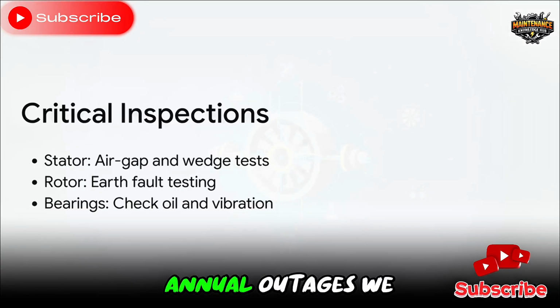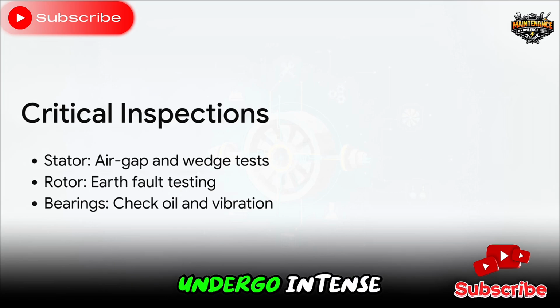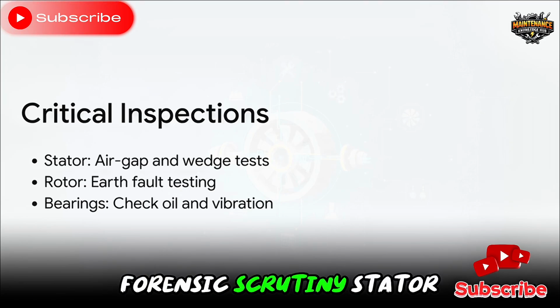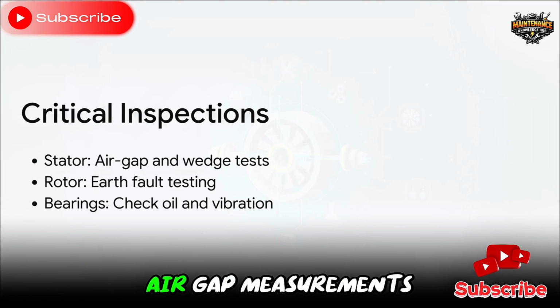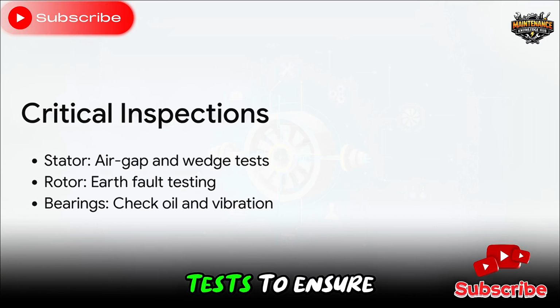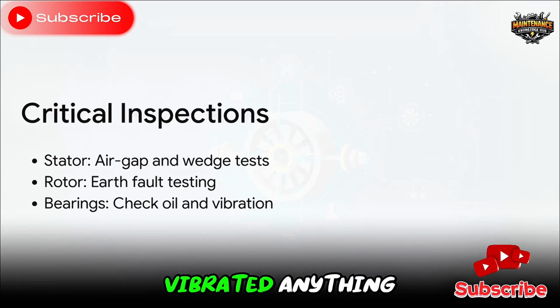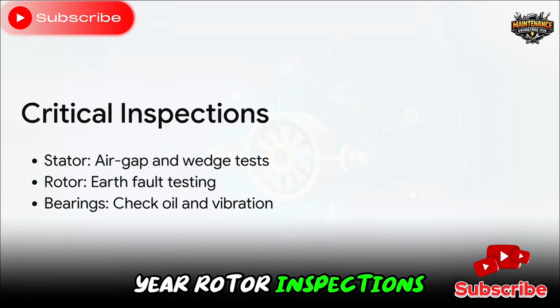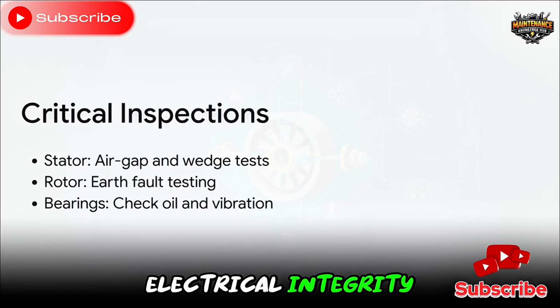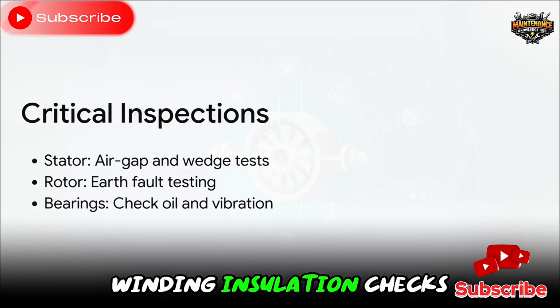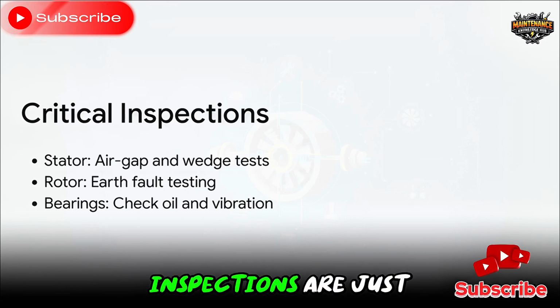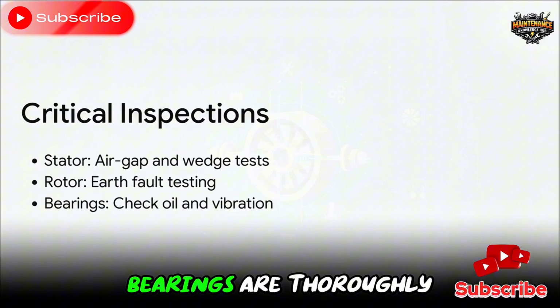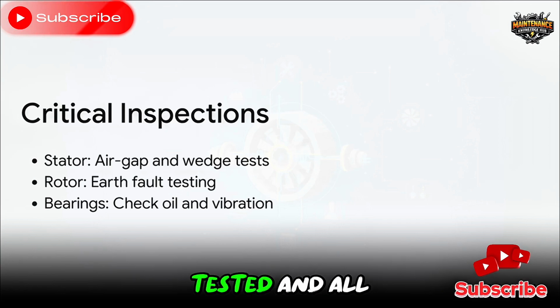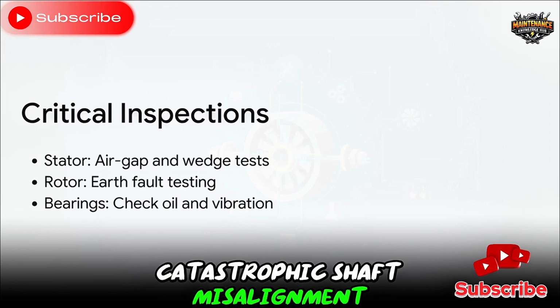During those big annual outages we talked about, these critical systems undergo intense forensic scrutiny. Stator inspections include incredibly precise air gap measurements and wedge tightness tests to ensure those massive magnetic forces haven't vibrated anything loose over the year. Rotor inspections focus heavily on electrical integrity, performing earth fault testing and field winding insulation checks. And finally, bearing inspections are just vital. Journal and thrust bearings are thoroughly checked, oil quality is tested, and all that continuous vibration monitoring data is analyzed. Catching a worn bearing early is exactly how you prevent catastrophic shaft misalignment.